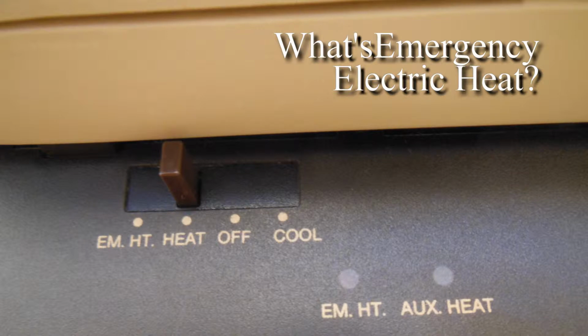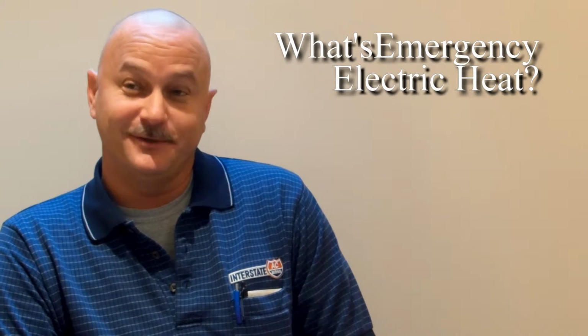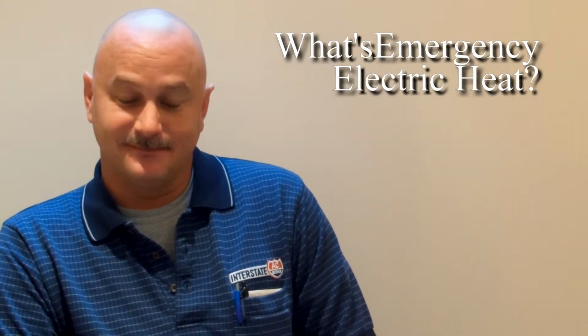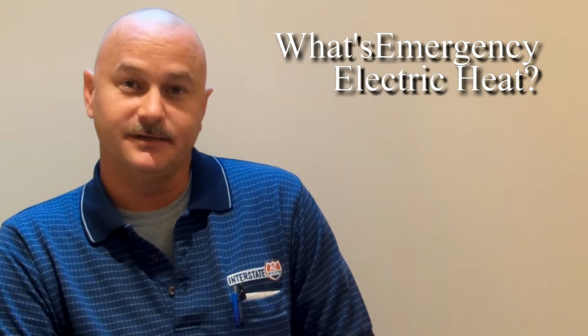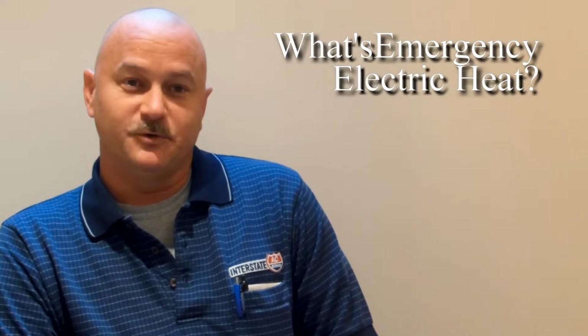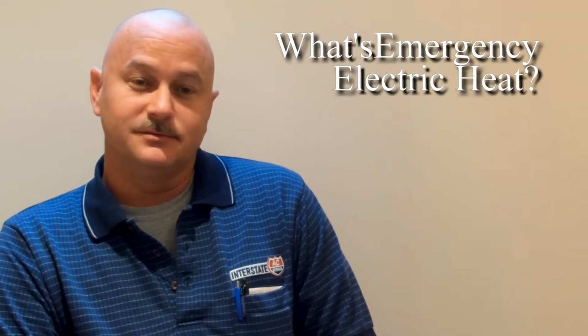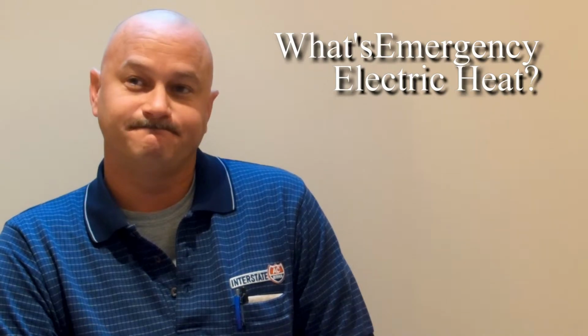Well, technically it's not an emergency electric. Your electric is an auxiliary heat. When you turn it on to emergency heat, then that turns off the compressor outside and only runs on the electric heat. That is a big misconception that a lot of people have, that their emergency heat is their electric heat. Their electric heat does not come on until the thermostat tells it to.